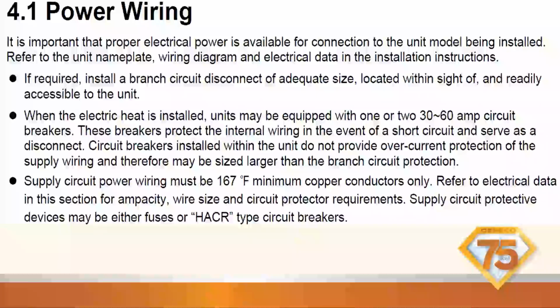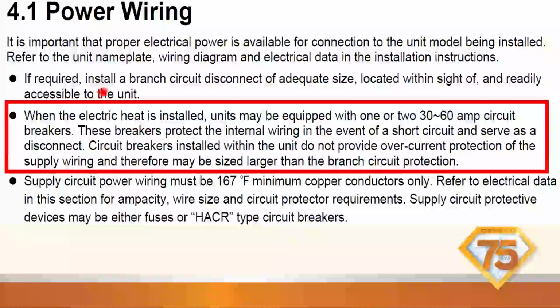Incoming line voltage. It is important that the proper electrical power is available for connection to the unit model; refer to the unit nameplate and wiring diagram. We still see this quite a bit: this should be up to a licensed electrician, who sizes the conductor of your line voltage per the amperage of the unit. If you have electrical inspectors out there, they'll look for that too. But if we don't have an inspector, some electricians will assume the wiring is correct because it's a retrofit, a direct swap out, and reuse the existing line voltage wiring.